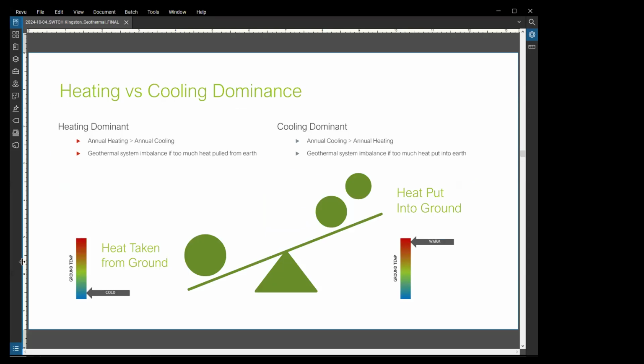We talked about Ontario being a heating dominant climate, in the sense that we're heating more of the year than we're cooling. What does that do to our geothermal field in terms of the balance we're trying to achieve at the end of every year? In a heating dominant climate, it becomes trickier to balance the field. If you think about a cooling dominant climate first, that's a climate where you're air conditioning more than heating, meaning you're putting more heat into the ground than you're taking out.